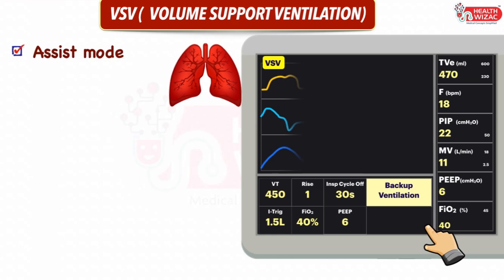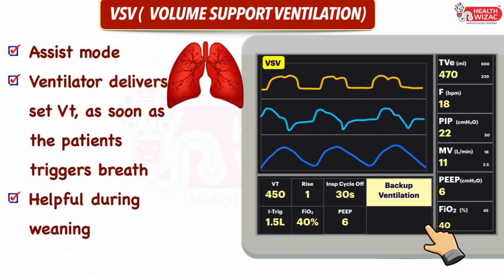Next is volume support ventilation. In this mode we have to set tidal volume, rise time, inspiratory trigger, FiO2, PEEP, inspiratory cycle off time, and backup ventilation settings. It is an assist mode of ventilation in which the ventilator delivers the set tidal volume as soon as the patient triggers breathing; however, if the patient fails to do so, the ventilator goes to backup ventilation. This mode is very helpful during the weaning process.